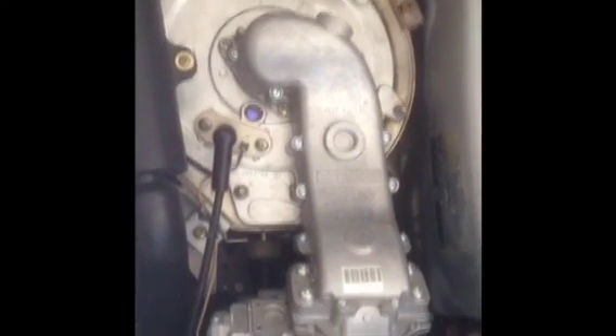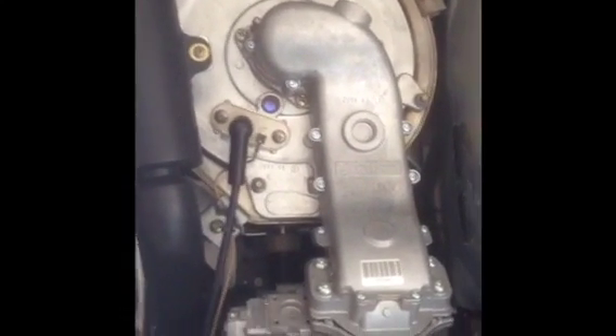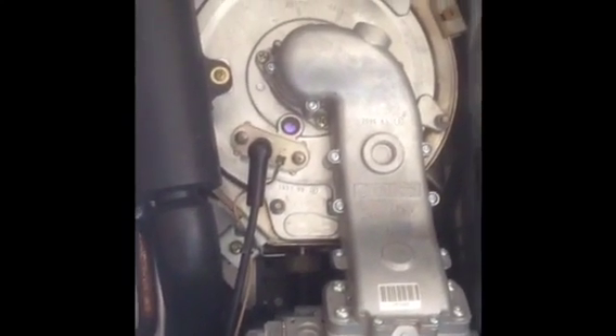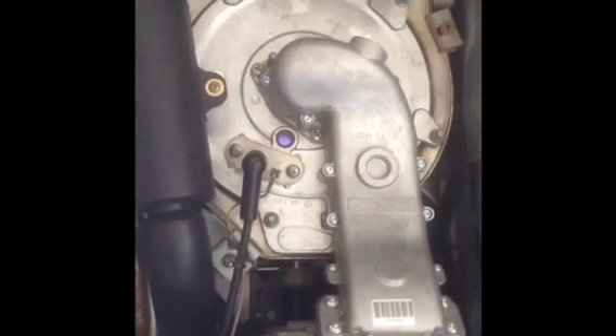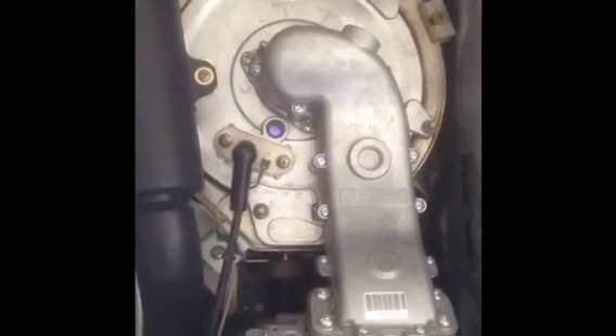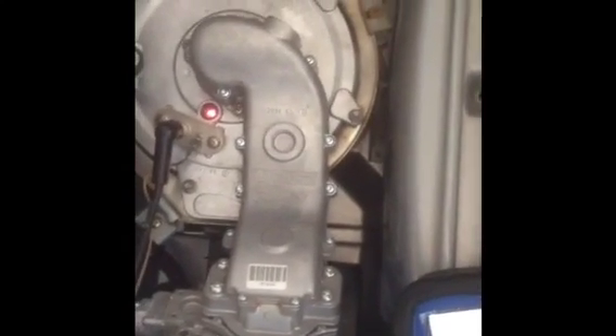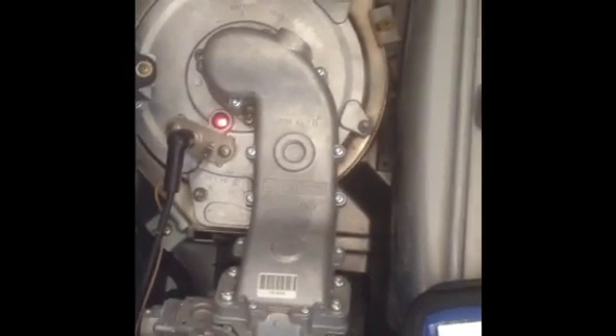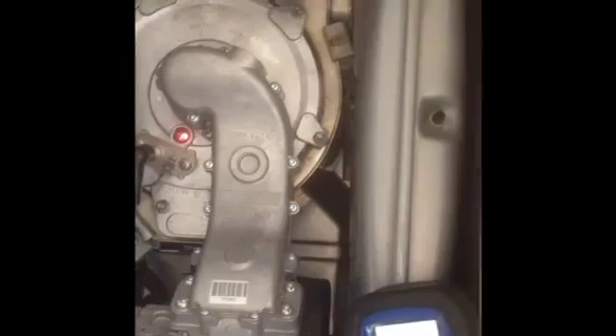We have now reassembled it and put it back on the boiler. And now we're using our flue gas analyzer, doing the carbon monoxide test. Right, finished the reading on the flue gas analyzer. 0.0008, so that was fine. So now we're doing a carbon monoxide test in the room to make quite sure it's safe.